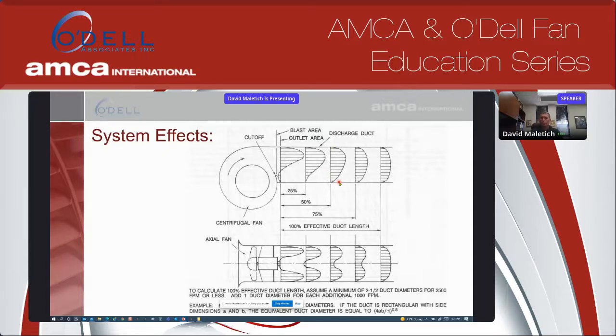And what's important about this is if you have something, like a wall or something out there, that prevents you from having your 100% of effective duct length, better have something than nothing. So just don't give up on it. If you can get 50% of your effective duct length, you're going to get 80% of your regain back. That's a very significant improvement. The remainder of this area from 50 to 100 is what I typically call a polishing area. You get an improvement, but it's not as significant of an improvement as that first 50%.